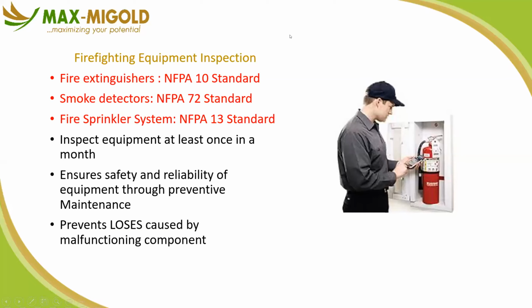Same thing applies with fire safety. Reliability is key, and you need not depend on one smoke detector, or have all smoke detectors on one panel just to save cost. Instead of having an 8-zone panel, on each zone you can actually wire 3, 4, or even more locations.